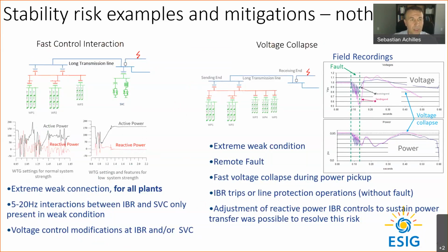Concentrating on the problem on the left, there are three inverter-based resource plants connected through a long transmission line, through a substation that has an SVC, and then through a couple of long lines to the rest of the network. There's a particular contingency that consists of losing one of these lines, resulting in the system becoming extremely weak - meaning the injection of current from these inverter-based resources has a significant effect on the network voltages.